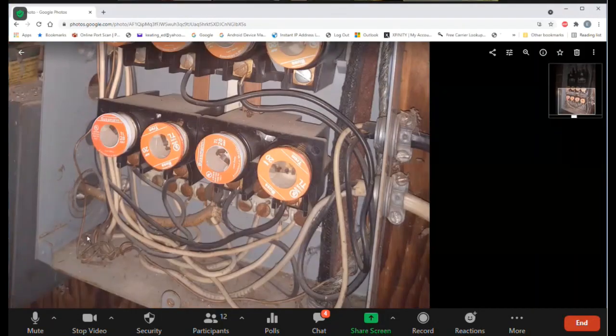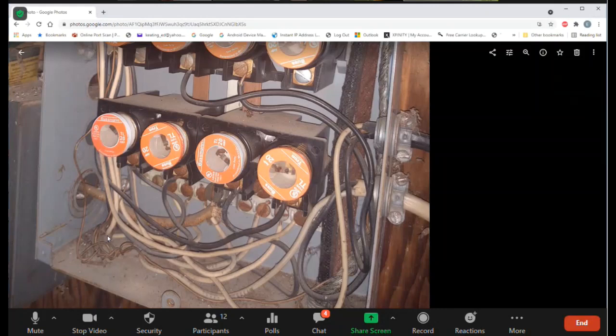The other thing is, you can see there are ground wires for all the cables coming in, but not all of those ground wires are connected to the 3-prong outlets in the wall. I plug in my tester on the 3-prong outlets and it says open ground, open ground. Plug it into the GFCI, open ground. Plug it into another GFCI, open ground. Plug it into a third GFCI, this one's wired correctly. I was kind of surprised by the ones I found that were actually wired correctly.